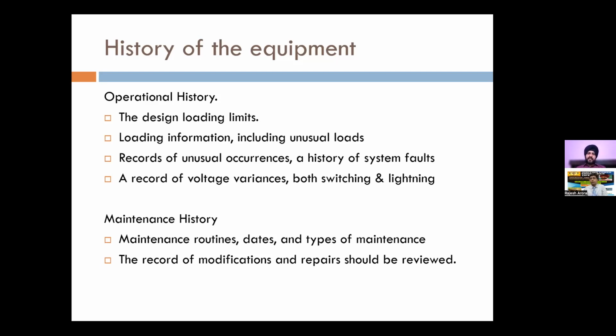Then if there have been any unusual loading, extremely high loading, or cycles of high loading followed by rapid cooling, so those kind of things. And if there have been any unusual occurrences like system faults or lightning or frequent switching, so all these factors constitute its operational history, which should be considered.